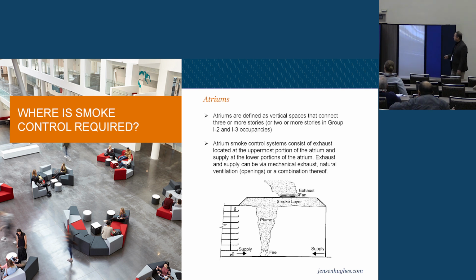Atrium smoke control systems are typically built off exhaust-based solutions and have a whole lot of complexity to them that you may not be thinking about. We'll talk about this one in detail, but usually there's an exhaust fan at the top, and then we have makeup air somehow, right? If you pull out too much air, you get a negative differential in the building, and you're probably just pulling air from everywhere. So likely there are doors that automatically open, louvers that automatically open, supply fans that come on in lower levels and help air come in the bottom, and we pull it out the top. The objective is to keep that smoke layer above the top level and above occupants, and we'll talk about that more in a minute.